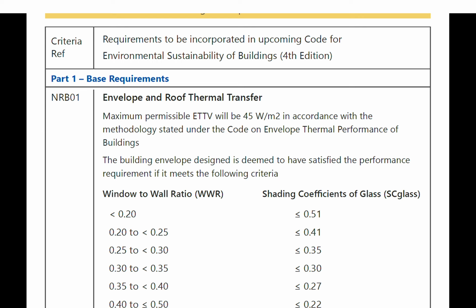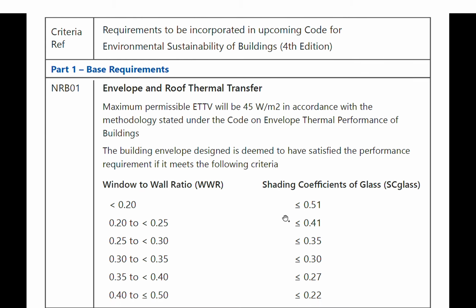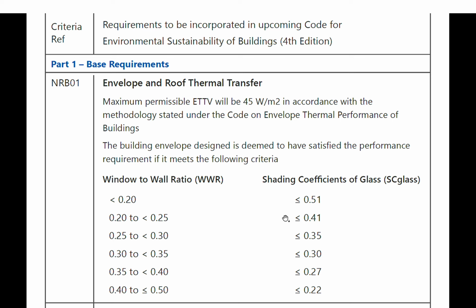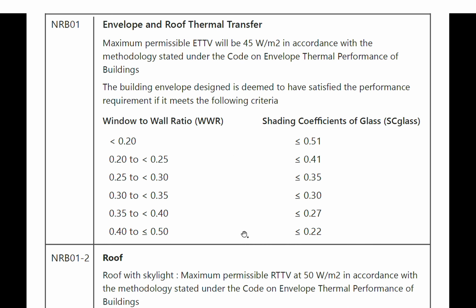So NRB01, envelope thermal transfer of roof and walls. So this is a little bit higher in terms of maximum permissible, which is approximately about 45 watts per meter square. So it's according to some methodology in the code of envelope thermal performance of the building, right? So the building design is deemed to have satisfactory performance if it meets some wall to window to wall ratio and shading coefficient of the glass, right? So this is basically the whole idea of having a better thermal efficiency in terms of the heat transfer.